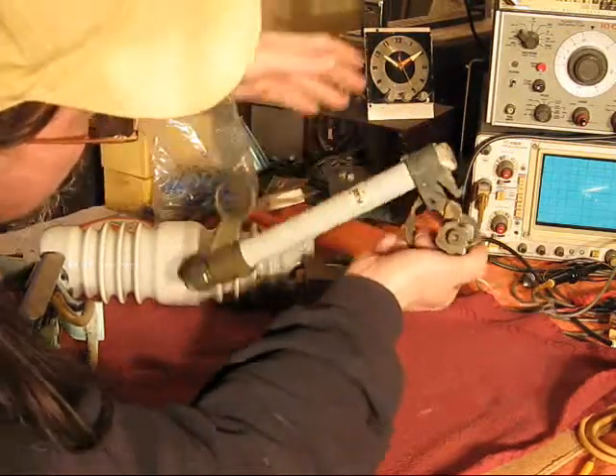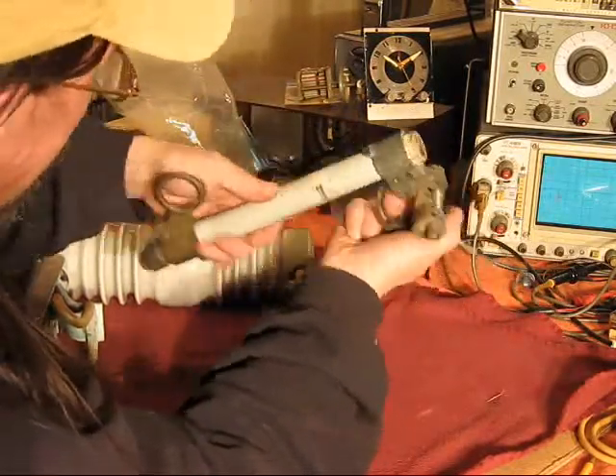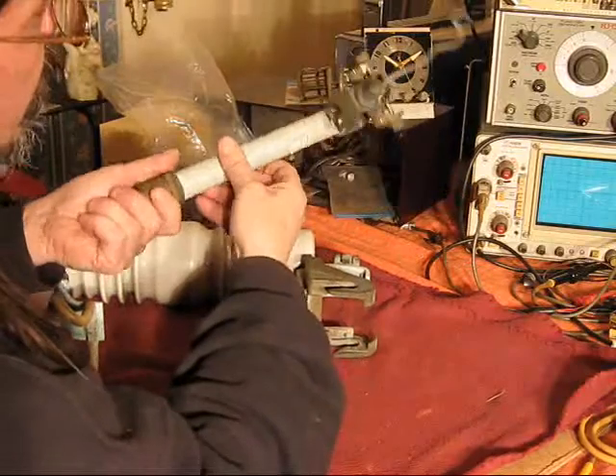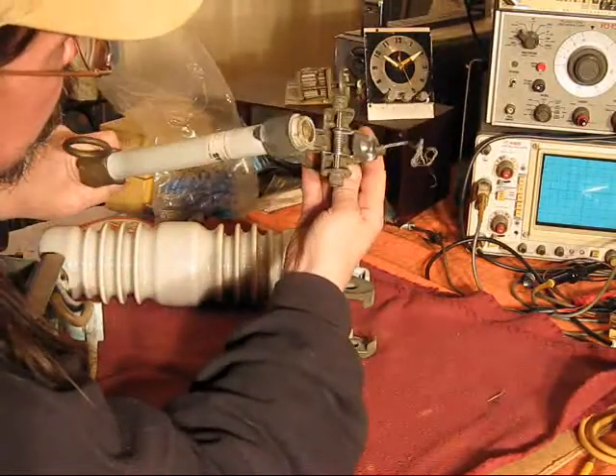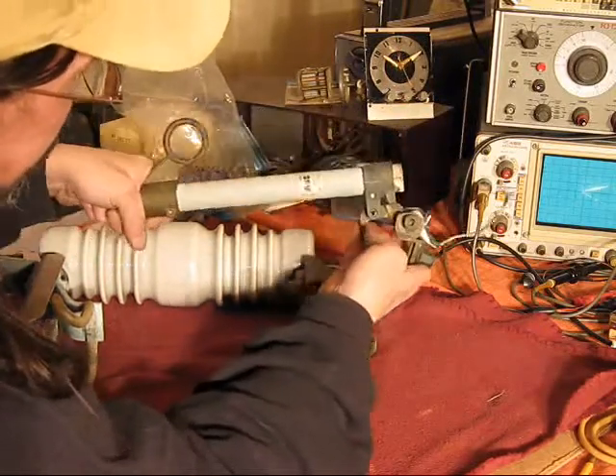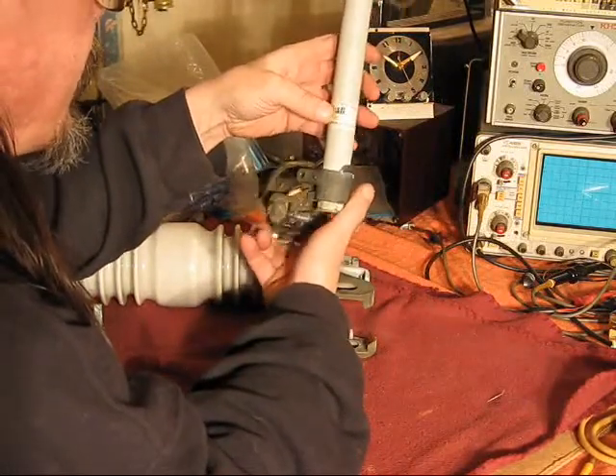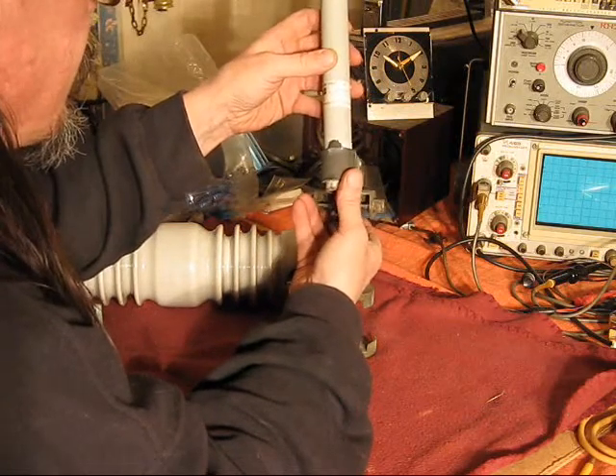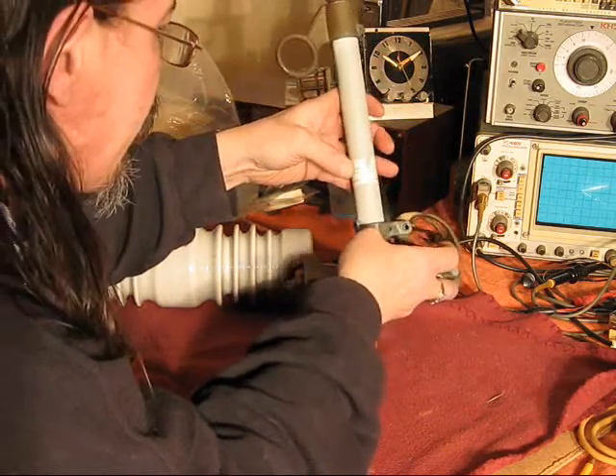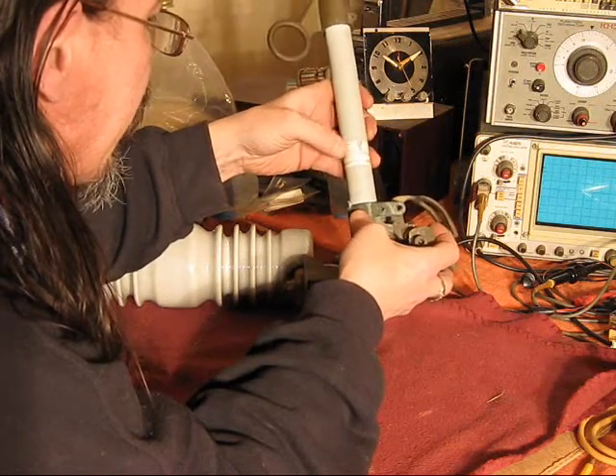So by that, it indicates to someone standing down on the ground, you can see up there it's dropped out of the holder. Kind of ingenious. And I'm sure there's quite a bit more to it than I'm aware of, but that's how this one looks. As far as this fuse goes, yes, it's a 15,000 volt fuse, 100 amp. Looks like it says 10,000 amp, probably interrupting capacity.